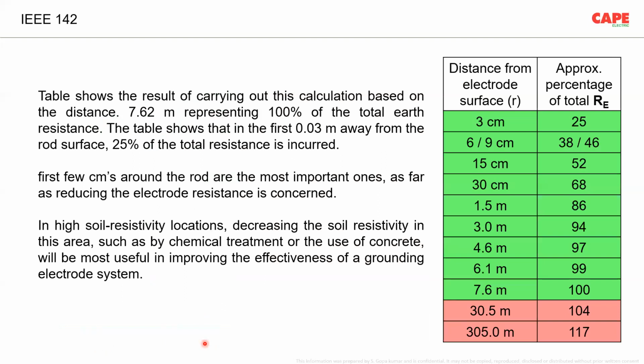Technically, it is not. So in the IEEE 142, you can find this particular table. They started measuring the resistance of the earth electrode with respect to the distance, and for approximately a 3-meter rod, within 7.6 meters the 100% value is achieved. But the measurement is still carried on at a longer distance, 30 meters, 300 meters. Still lower resistance values are possible, but the influence of this area is not significant with respect to the increase in the distance.